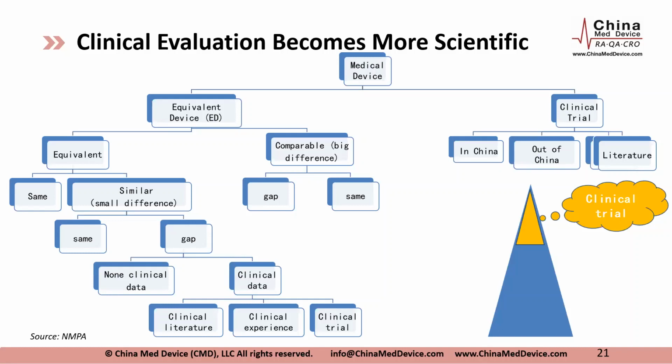So look at the equivalency or comparable. There are specific guidance documents there. And look at the gap. If it's the same, you don't have to justify. If there is a gap, whether it's small differences or large differences, you pretty much justify the gap through non-clinical or clinical data. When it comes to clinical data, the data source is the key.